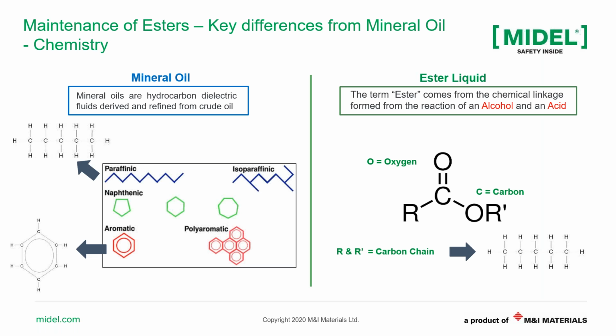For this, we really need to appreciate the difference in chemistry between mineral oil and ester liquid. Mineral oil is a hydrocarbon oil derived from crude petroleum oils, and so it can be composed of different molecular structures, paraffinic, naphthenic, aromatic, and so on, in different ratios to provide certain parameters. But basically, the main building blocks of mineral oil are hydrogen and carbon, so it's a hydrocarbon. Anything produced from mineral oil due to a fault will be based on carbon and hydrogen.